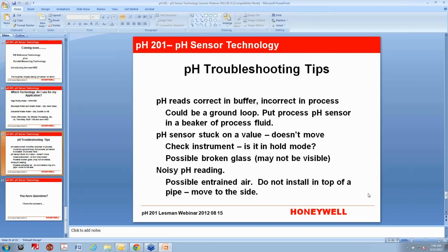You can't always see broken glass. If you have a sensor that you have threaded into a line and somebody has used a pair of channel locks on it to tighten it or to loosen it, that twisting motion can cause the glass inside, that glass stem that runs the length of the sensor, to get a tiny crack in it. You'll never see it because it's inside the sensor, but it will, over a small amount of time, create a liquid path between the reference, which surrounds it, and inside the glass where the measuring electrode is. And when that happens, it usually sticks on something. So you don't want to ever use channel locks on your pH sensors unless you're just taking it out to throw it away.